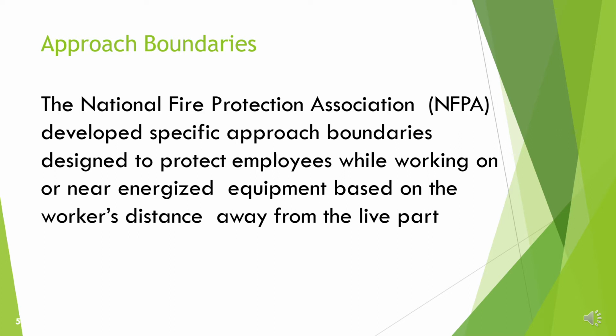Now we're going to talk about approach boundaries, and these are created and updated by the National Fire Protection Association, commonly known as NFPA. So when we're looking at specific electrical standards, we're looking at NFPA 70E. As far as OSHA is concerned, OSHA just spells out and tells the employer that they have to protect their employee, but they don't actually go into the real specifics of how to do that. That's why NFPA 70E is referenced when an employer is looking at how to protect their employees. So they develop specific approach boundaries that are designed to protect employees while working on or near energized equipment, based on a worker's distance away from a live part. The distances will increase and decrease dependent on what qualifications you have, and also how large the source or voltage is that you're going to be working around.